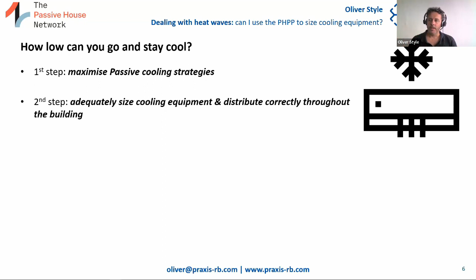The second step is to size that kit correctly, because passive house buildings are different to conventional buildings. The rule of thumb an installer or engineer may apply to a conventional building won't be appropriate here, it'll be oversized. So we need to size the cooling equipment correctly and distribute it throughout the building, getting heat out equally in all the different spaces, taking into account different orientations, heat gains, and occupancy gains.